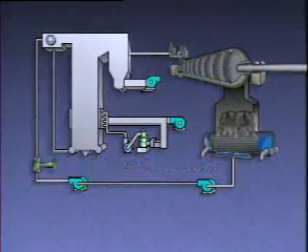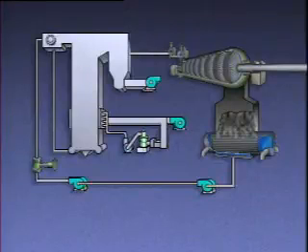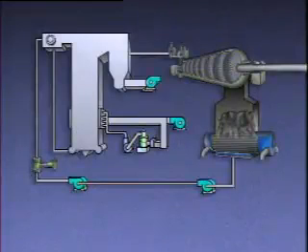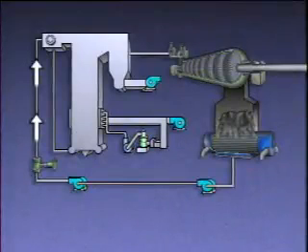The condensate feed water system is actually made up of two systems. The condensate system removes the condensate from the hot well. Then the feed water system feeds it back to the boiler. The water that is pumped into the boiler is called feed water. It replaces the water that leaves the boiler as steam.